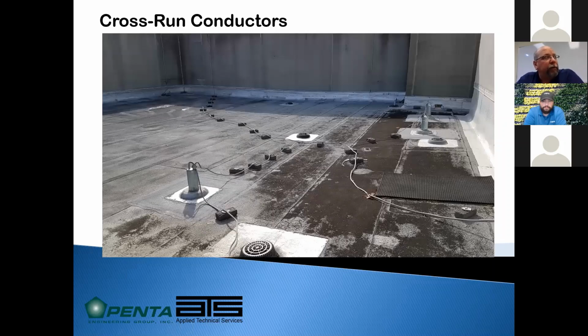This is a roof that probably was initially a ballasted roof. And for those that don't know, a ballasted roof is covered with river rock or stone or some type of other gravel aggregate. It was replaced with a rolled roof, but they left all of the standoff blocks, and these are no longer spaced at 3-foot intervals, so our conductor is not securely fastened every 3 feet. This is also a bonding connection to a tie-back safety anchor that a window washer would tie off to. And they attached it in a manner that really limits the use of that anchor and could potentially cause a dangerous situation for anyone using that.